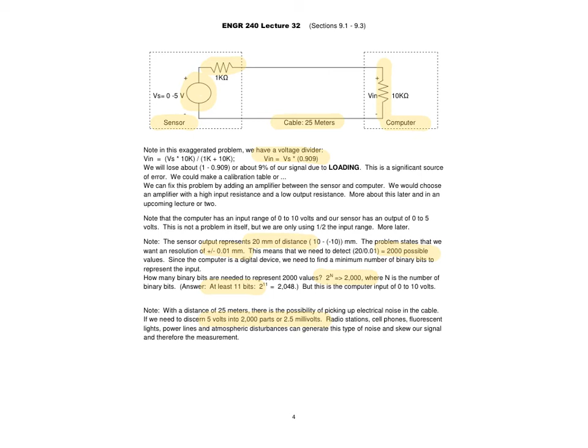So here we've modified our original diagram a little bit. Because the computer can accept 0 to 10 volts and we are providing 0 to 5 volts, we are not using the full resolution of the computer. That means we either need to have 12 bits in order to get our required accuracy, or we could add a small amplifier with a gain of 2 so that our 0 to 5 volt signal now becomes a 0 to 10 volt signal and more closely matches the input of the computer.